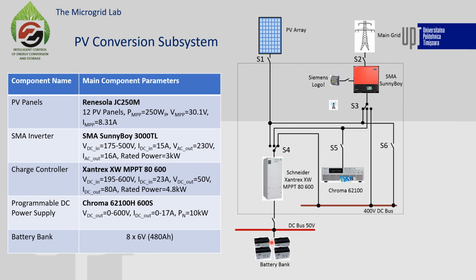Depending on the state of switches S1 up to S6, there are many configuration possibilities for subsystem operation. For example, in the actual configuration of the microgrid, where the PV panels are connected directly to the high voltage DC bus, switches S1 and S6 are closed, while S4 and S3 are in the third position, meaning there is a connection with the main grid.